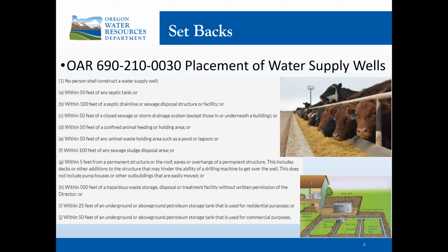Additionally, the 5-foot setback to permanent structures or roofs is a very common issue, and it really adversely affects the future of the well, of it being able to be repaired if needed, or if there are issues with the pump apparatus, by building over them. It really interferes with that. So those are the real takeaways of that.